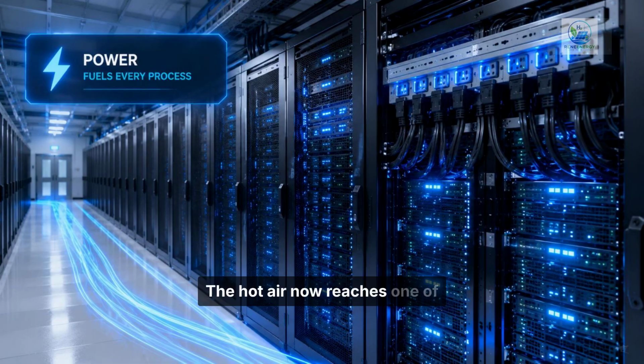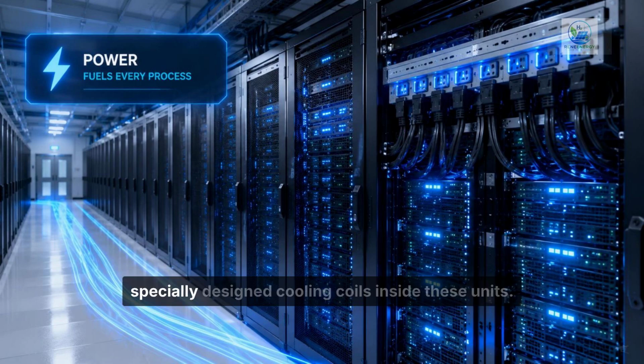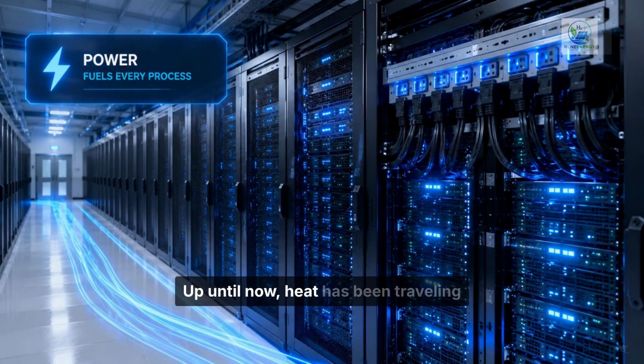The hot air now reaches one of the most important machines inside the data center, the Computer Room Air Handler, or CRAH, and in some facilities, the Computer Room Air Conditioner, or CRAC. Large fans pull the hot air through specially designed cooling coils inside these units. At this moment, the journey changes. Up until now, heat has been traveling through air. But inside the CRAH, that heat is transferred into a completely different medium: water.